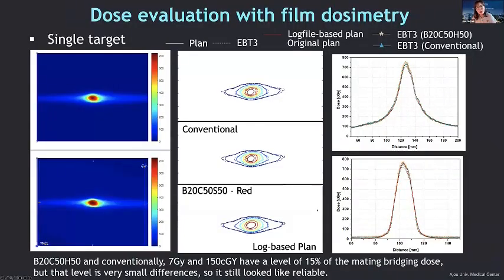The single target field measurement results are shown here. We brought all of that into the analysis software, our in-house software. You can see the film results here, with brightness 20 and contrast and highlight 50, plotted against the conventional one. The 7 gray and 150 centigray levels have about 15% matched bridging doses. But the level of difference is very small, so it still looks very reliable between the two plots.